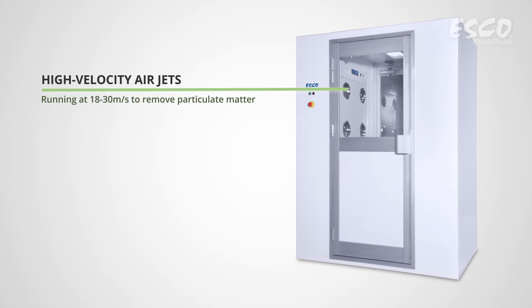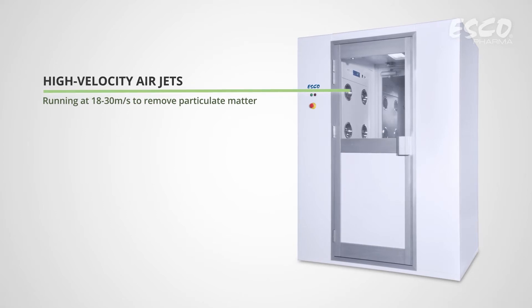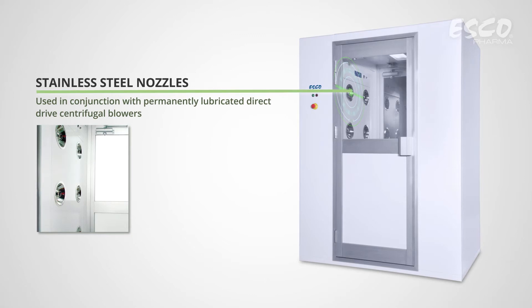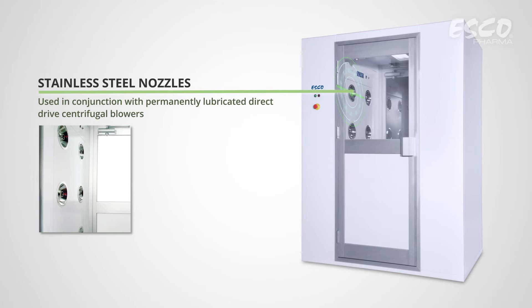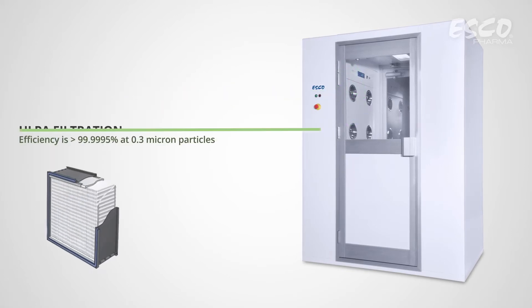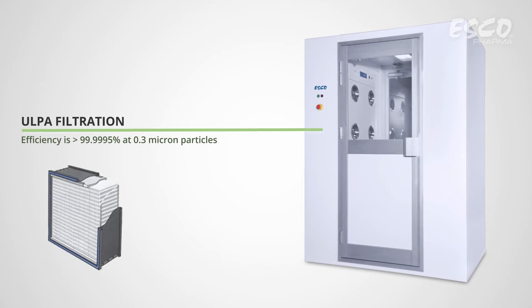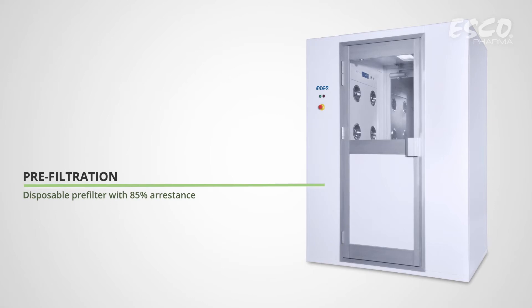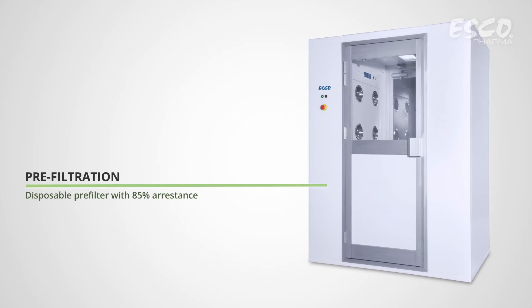High-velocity shower jets running at 18 to 30 meters per second ensure efficient scrubbing action to remove particulate matter. Permanently lubricated direct-drive centrifugal blowers are used in conjunction with stainless steel air nozzles. The typical efficiency of the ULPA filter is greater than 99.9995% at 0.3 micron particles. A disposable pre-filter with 85% efficiency extends the life of the main filter.